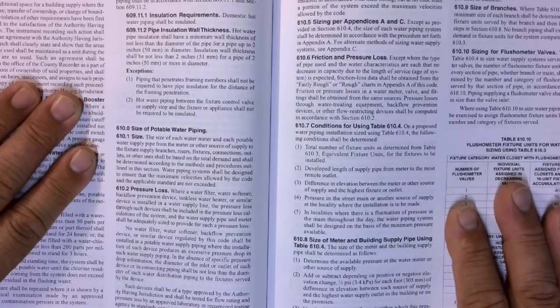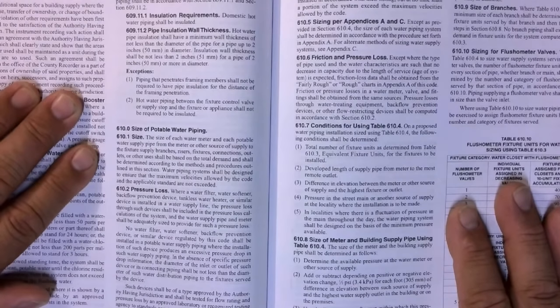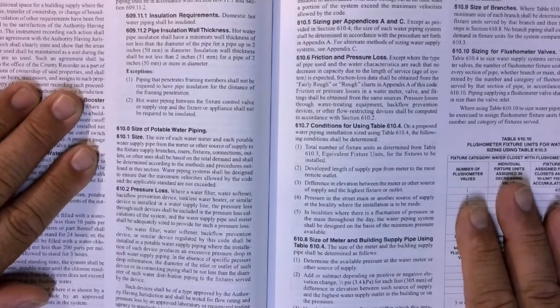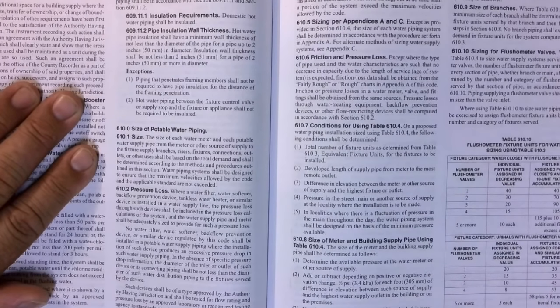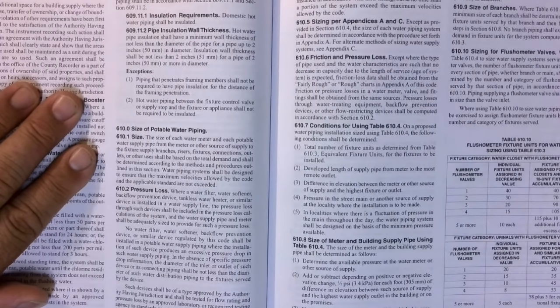are not exceeded. Where a water filter, water softener, backflow device, tankless water heater, or similar device is installed, the pressure loss through such devices shall be included in the pressure loss calculations of the system, and the water supply pipe and meter shall be adequately sized to provide for such a pressure loss. No water filter, water softener, backflow device, or similar device regulated by this code shall be installed in a potable water supply piping where the installation of such device produces an excessive pressure drop in such water supply piping.